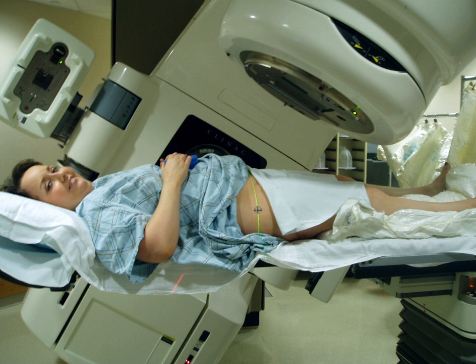It can be a magnetic transponder which senses the magnetic field generated by several transmitting coils, and then transmits the measurements back to the positioning system to determine the location. The implantable device can also be a small wireless transmitter sending out an RF signal, which then will be received by a sensor array and used for localization and real-time tracking of the tumor position.